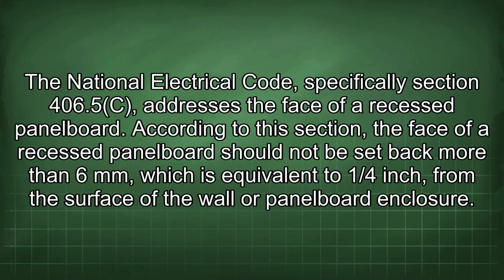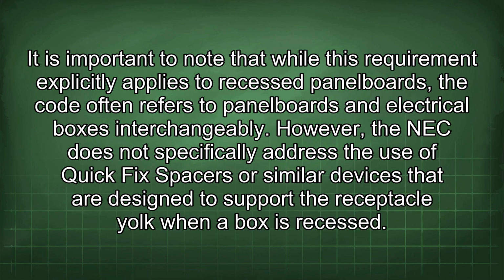The National Electrical Code, specifically Section 406.5c, addresses the face of a recessed panel board. According to the section, the face of a recessed panel board should not be set back more than 6 mm, which is equivalent to 1/4 inch, from the surface of the wall or panel board enclosure. It is important to note that while this requirement explicitly applies to recessed panel boards, the code often refers to panel boards and electrical boxes interchangeably.